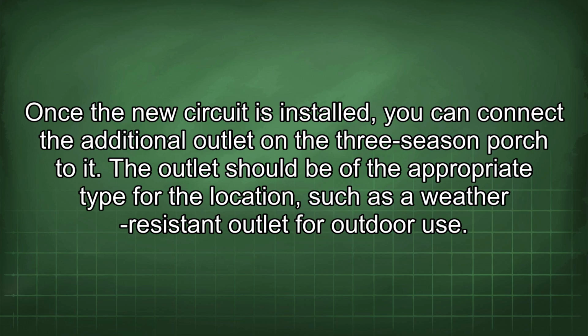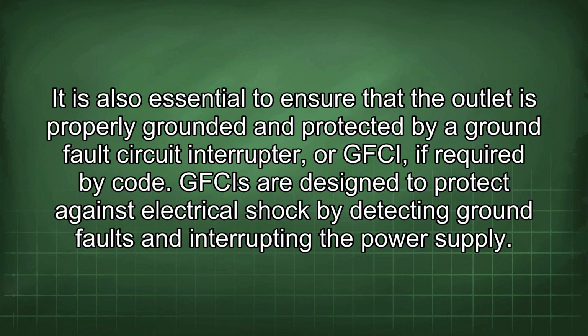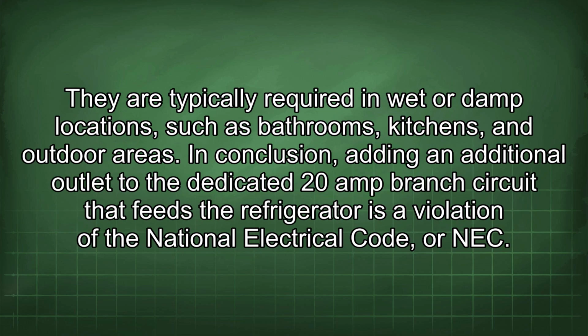The outlet should be of the appropriate type for the location, such as a weather-resistant outlet for outdoor use. It is also essential to ensure that the outlet is properly grounded and protected by a ground fault circuit interrupter, or GFCI, if required by code. GFCIs are designed to protect against electrical shock by detecting ground faults and interrupting the power supply. They are typically required in wet or damp locations such as bathrooms, kitchens, and outdoor areas.